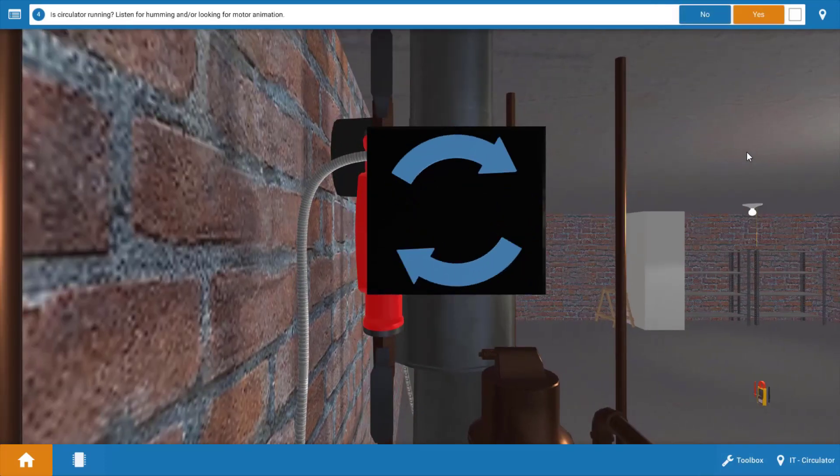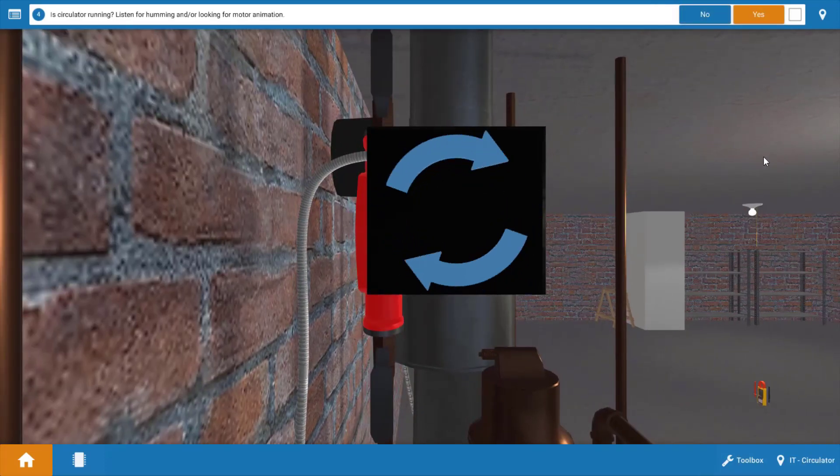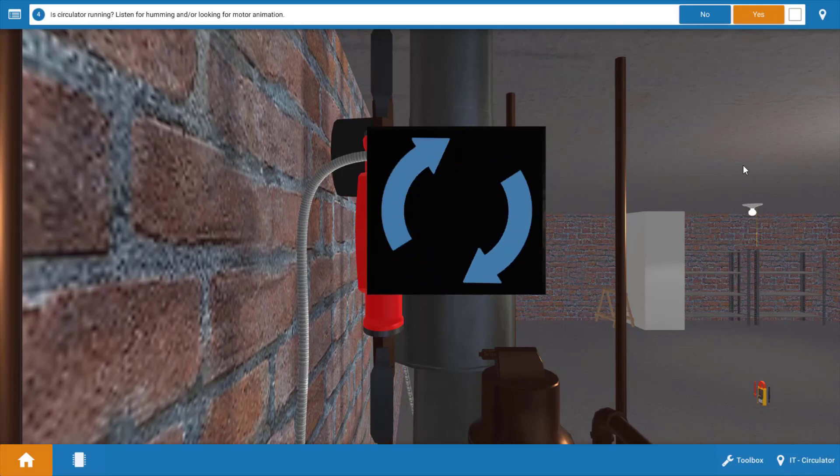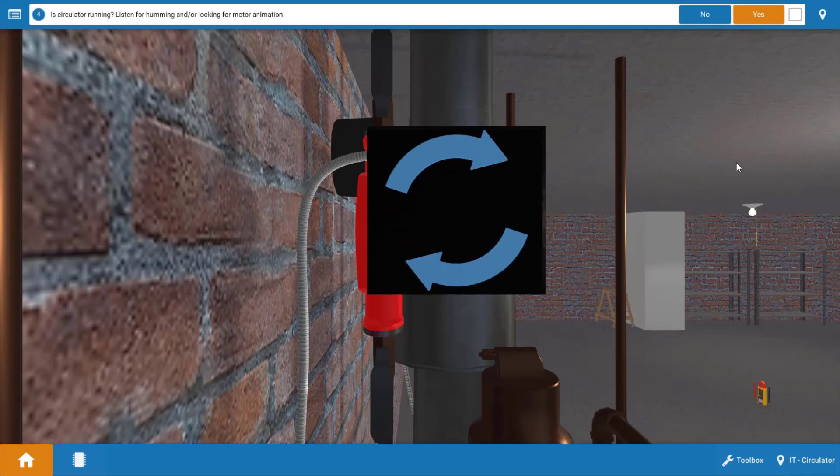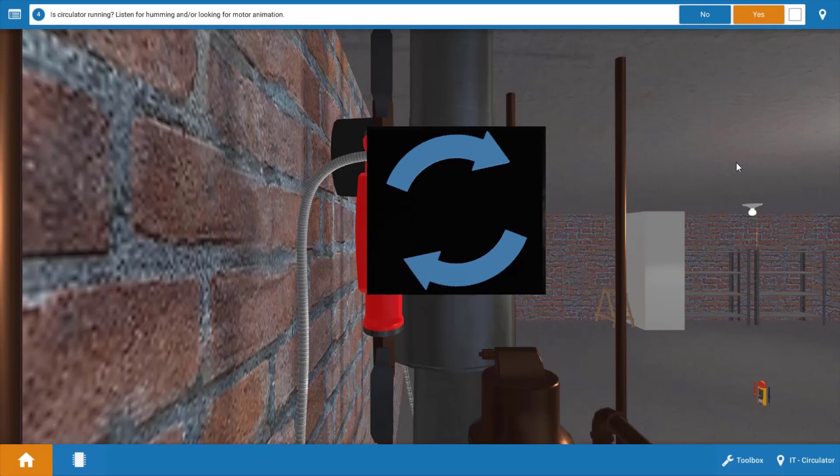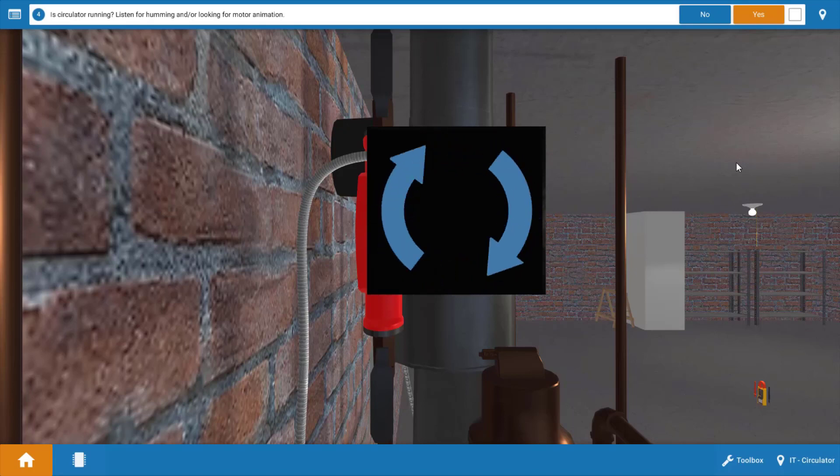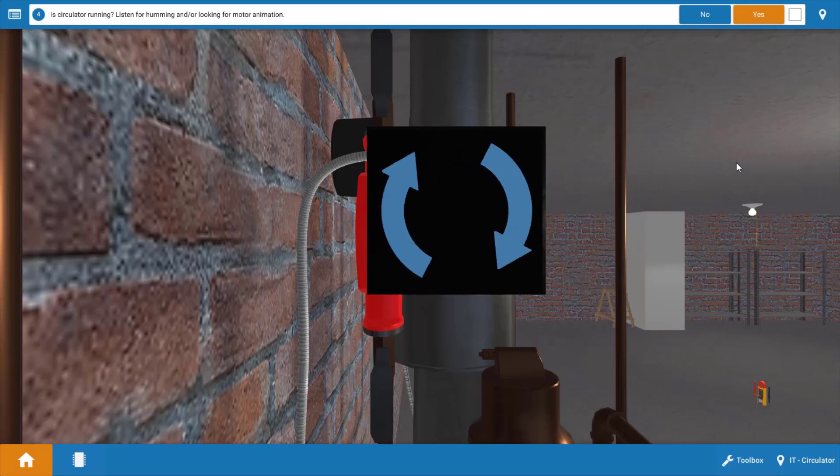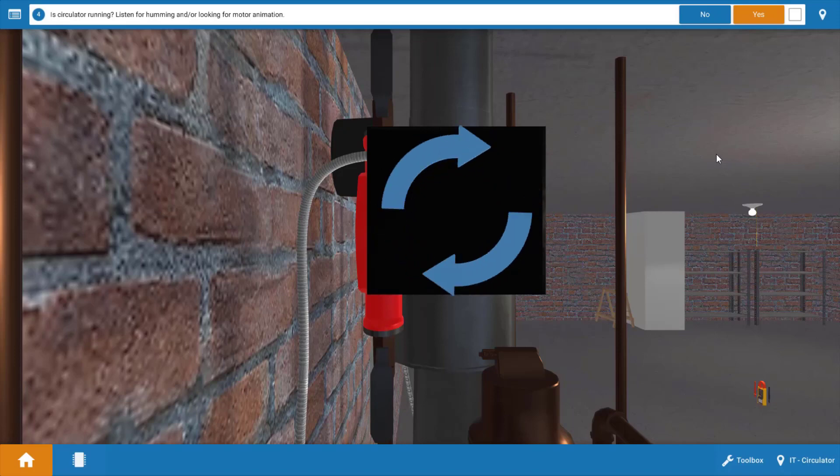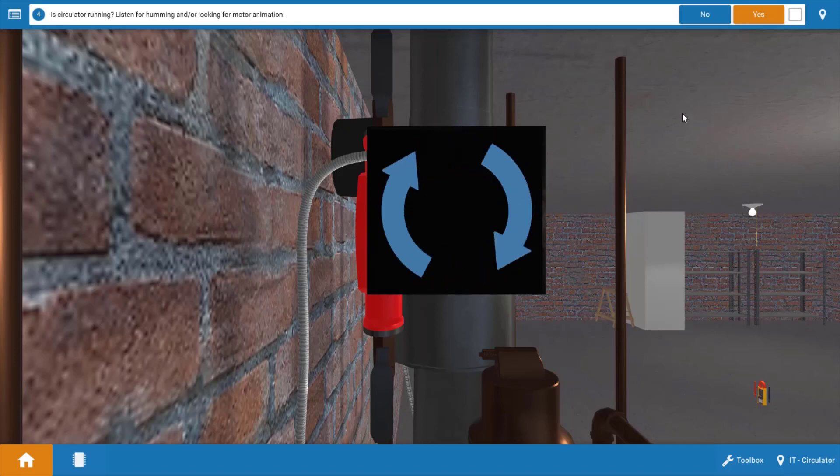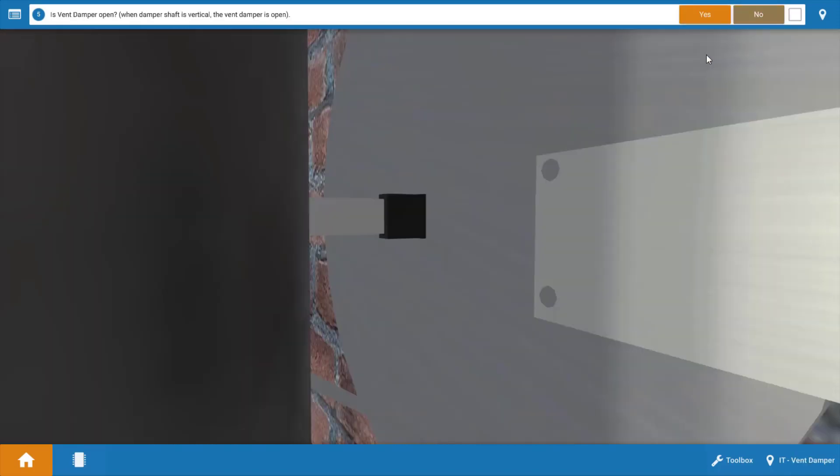Next, we're going to look at the circulator pump, and as evidenced by the spinning blue arrows, the circulator pump is running. Now you can check this with a digital clamp-on ammeter as well that will read fractional amperages, so you can verify if the circulator is running in that manner as well. So the circulator is in fact running.